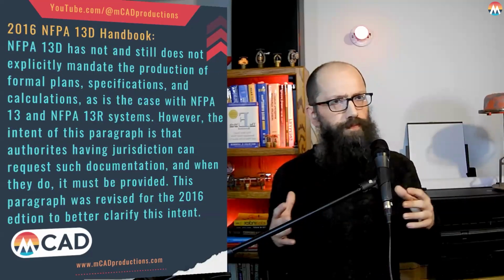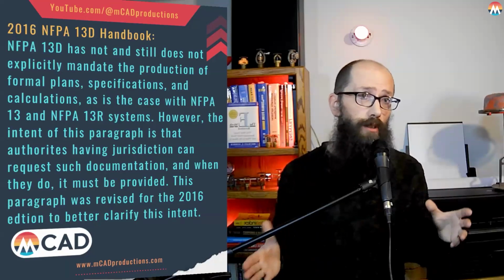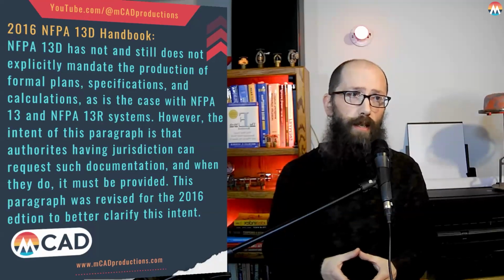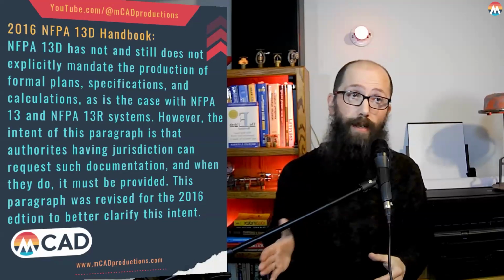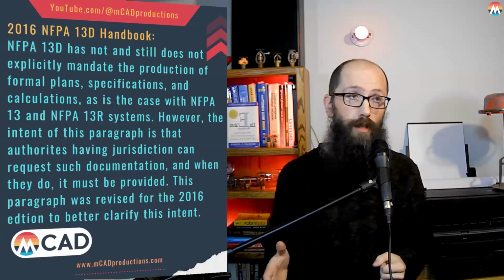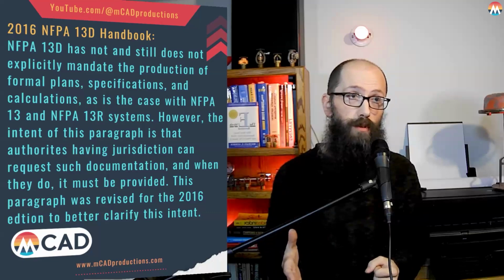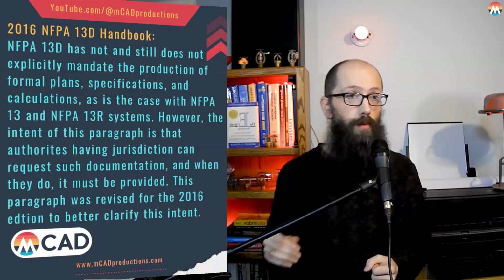It says, NFPA 13D has not and still does not explicitly mandate the production of formal plans, specifications, and calculations, as is the case with NFPA 13 and 13R systems. And like that whole sentence would blow a whole lot of plans examiners' minds just hearing that.